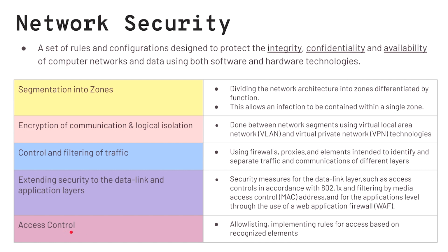And at the end, access control. In this context, you try to create a list of both who is accessing what, and also what computers are communicating with what computers, at which IPs and which ports. So you're creating rules about who has access to what, and the who again can be from human operators to computers to PLCs. Firewall rules of access, whitelist, allow listing, deny listing, and you have to create the rules to access, monitor, and filter traffic between only trusted and well-defined elements.